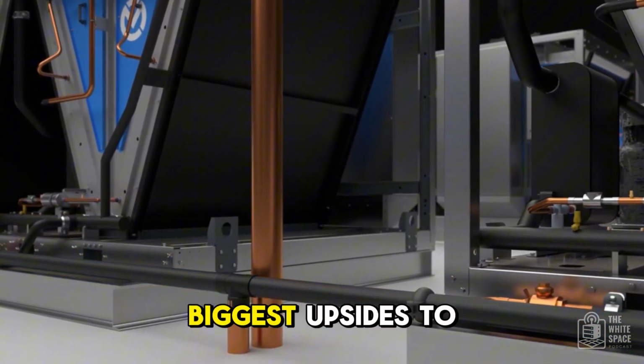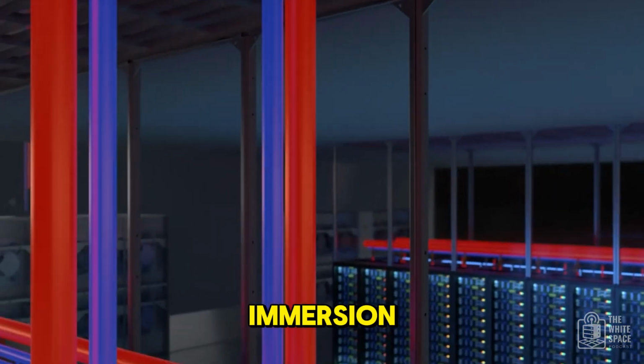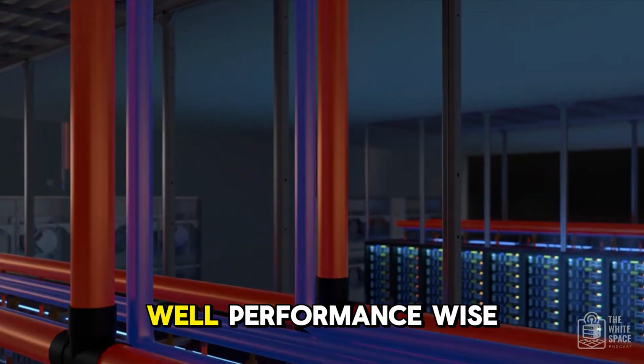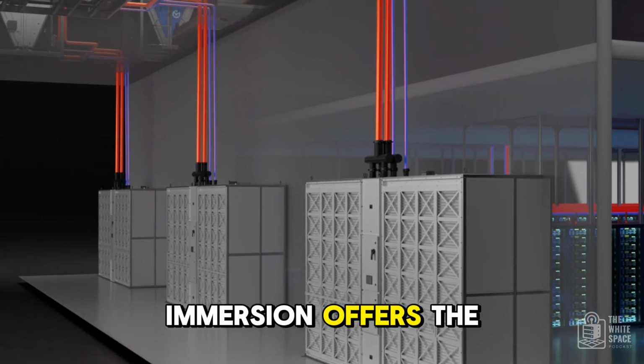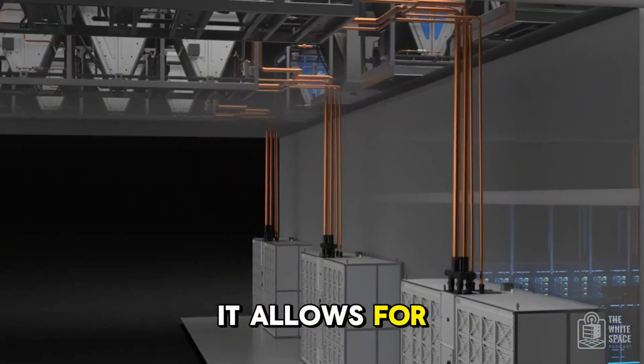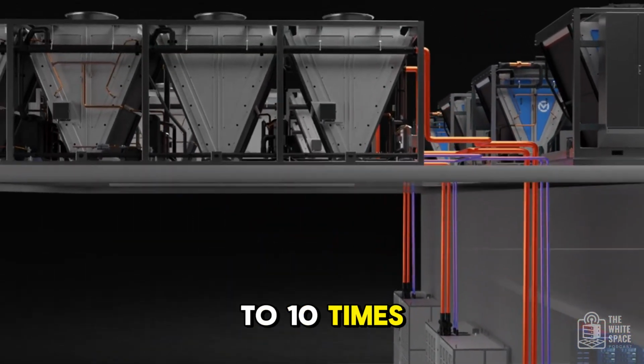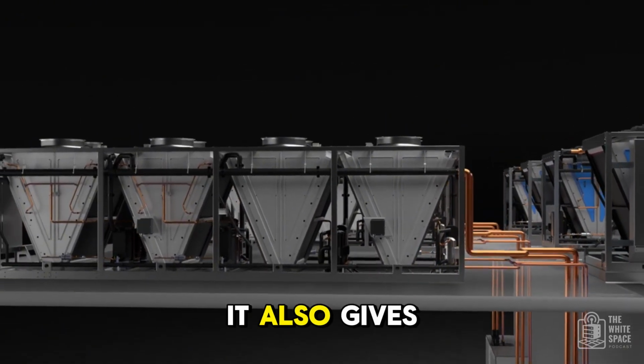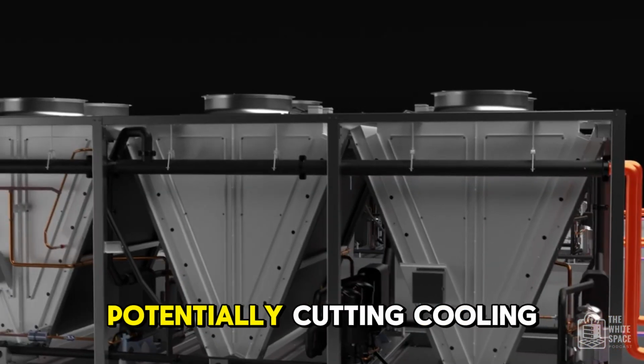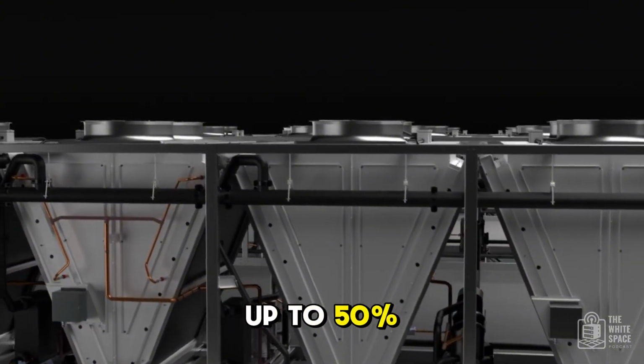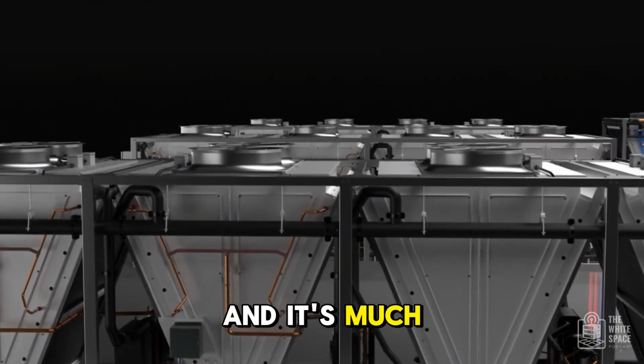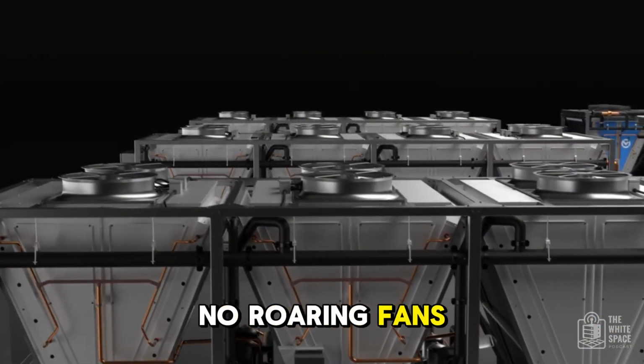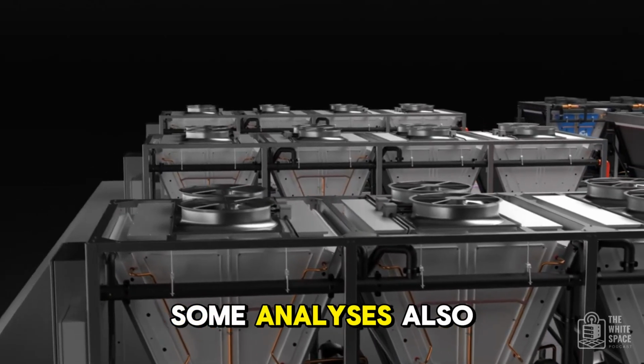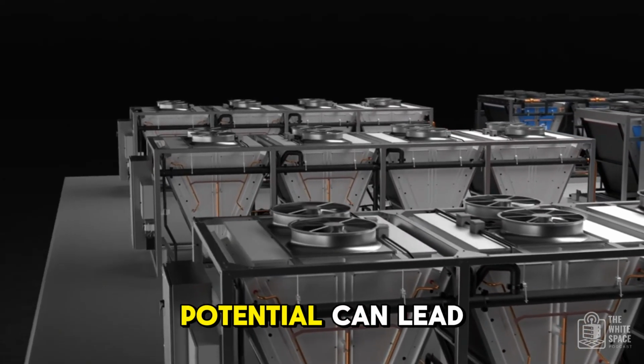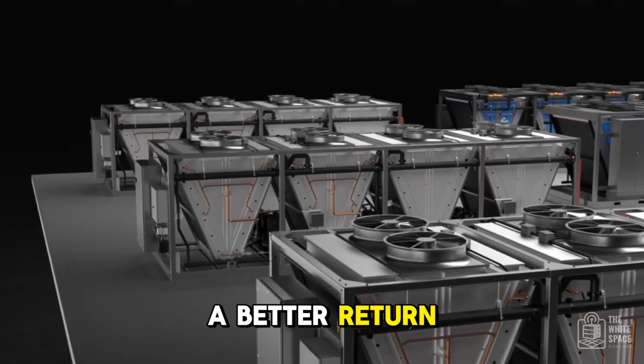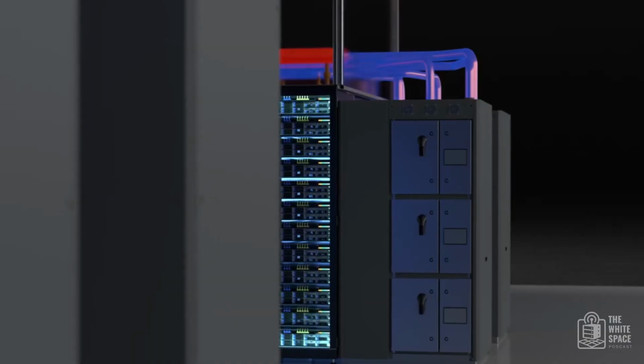Wow. So what are the biggest upsides to taking the plunge with immersion cooling in a big data center? Well, performance-wise, immersion offers the absolute best cooling. It allows for the highest rack densities, some say up to 10 times what air cooling can handle. It also gives you the best energy efficiency, potentially cutting cooling power usage by up to 50%. And it's much quieter, obviously, no roaring fans inside the tank. Some analyses also suggest that heat reuse potential can lead to a better ROI, a better return on investment over the long haul. Okay, super powerful.